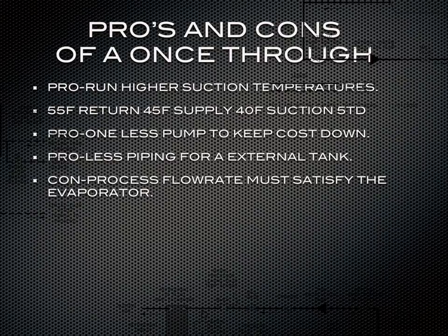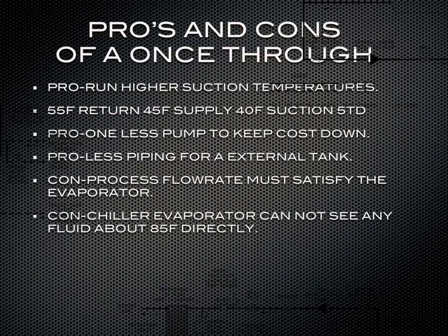Now, let's get into the cons here. Your process flow rate must satisfy the chiller evaporator. Because you have one loop and everything's so intertwined, you have to satisfy that chiller evaporator, and your process has to be built around the flow rate of the chiller evaporator. Another con is the chiller evaporator cannot see any fluids above 85 degrees F directly. If you introduce a fluid warmer than 85 degrees F, you're going to put too much heat into the refrigeration system and you won't be able to reject it, and your refrigeration system will shut down.